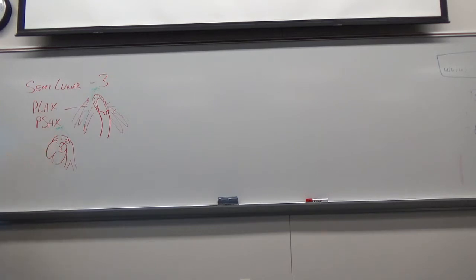My only caution to that is, especially when we use Zoom, and this week's lab we're adding Zoom, you want to bring the sector size down and set my depth appropriately before I go into Zoom. If I take this big huge sector and zoom in over in this little corner, it's still processing all that other stuff and it's still affecting your frame rate. So narrow it in. It will also give you tighter line density, so you get better detail resolution. That's important, especially when we get into Doppler.